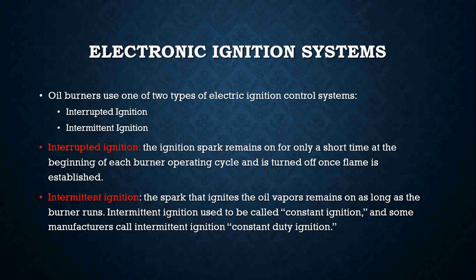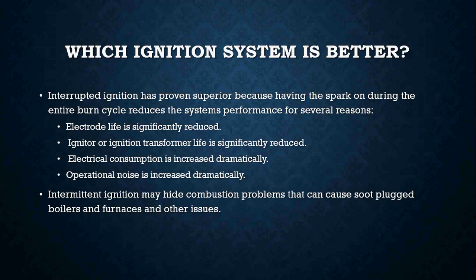Make sure you understand that interrupted ignition means the spark is on for a short period of time only to ignite the oil, and then it shuts off. Intermittent ignition means the spark is on all the time as long as the burner is operating. Interrupted ignition, however, is actually the better of the two.